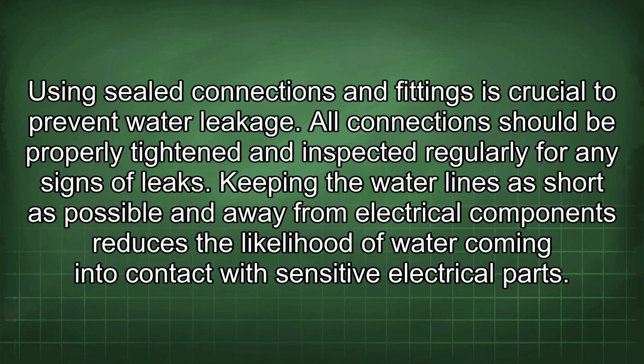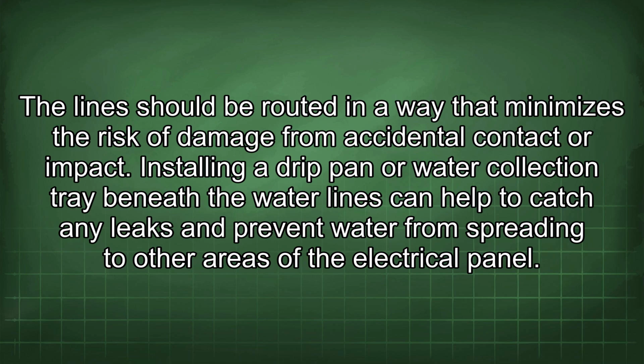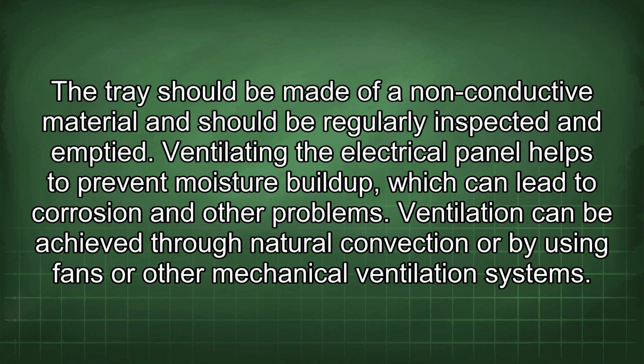Keeping the water lines as short as possible and away from electrical components reduces the likelihood of water coming into contact with sensitive electrical parts. The lines should be routed in a way that minimizes the risk of damage from accidental contact or impact. Installing a drip pan or water collection tray beneath the water lines can help to catch any leaks and prevent water from spreading to other areas of the electrical panel. The tray should be made of a non-conductive material and should be regularly inspected and emptied.